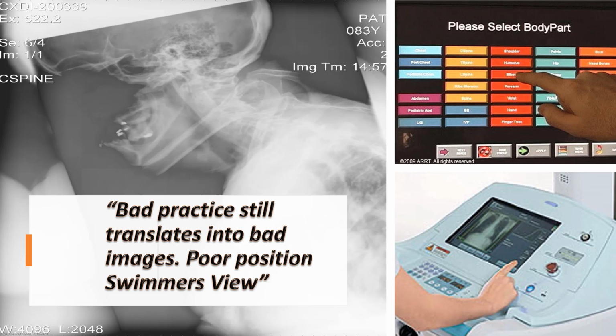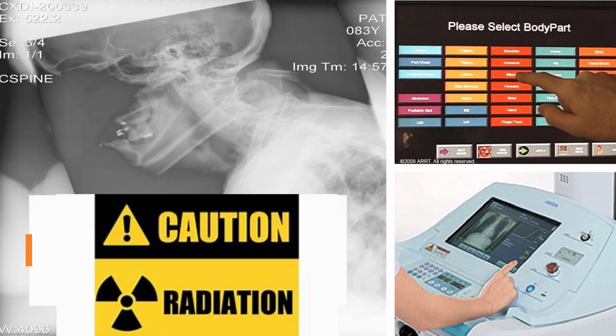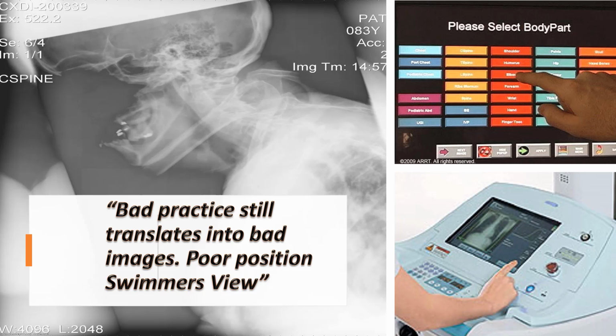Another practice we often see is somebody goes, oh, you know what? If you want to go upstairs and do a portable in the neonate unit, what I found is the best technique is just set it up on the anatomical programming for a finger. It works great. Well, yeah, that might work great for getting a capture of an image as far as you can see for the densities, but are the densities correct? And also, what is sent to the PACS, a finger or a portable chest x-ray?